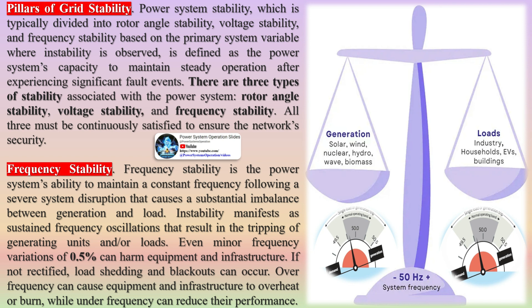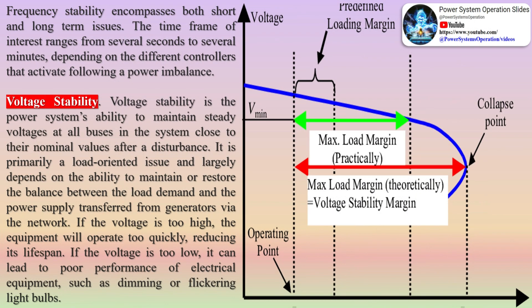Frequency stability is the power system's ability to maintain a constant frequency following a severe system disruption that causes a substantial imbalance between generation and load. Instability manifests as sustained frequency oscillations that result in the tripping of generating units and/or loads. Even minor frequency variations of 0.5 percent can harm equipment and infrastructure if not rectified, and load shedding and blackouts can occur.